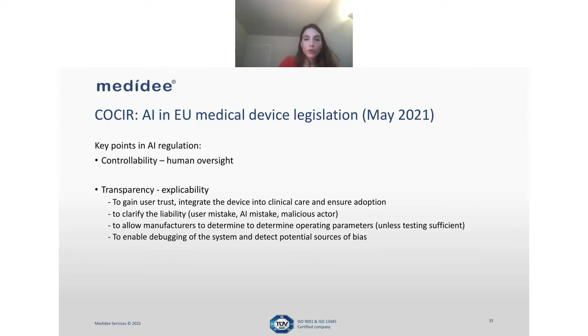So that's one point. Then also to clarify liability, right? So if you have a system that is transparent, then you're also able to pinpoint where the mistake has been made in any situation that is precarious. So was it a user mistake? Was it an AI mistake? Or maybe a cybersecurity problem? And additionally, having a system that has increased transparency can also aid actually the manufacturer and the developer of the device, in that they are able to maybe better determine operating parameters or to debug their system and pinpoint potential sources of bias.